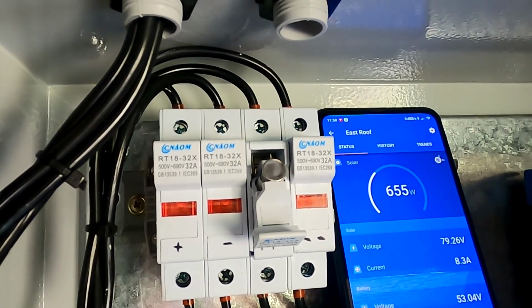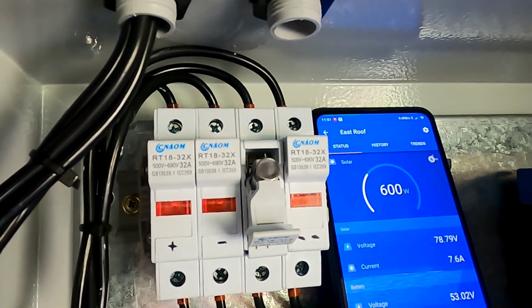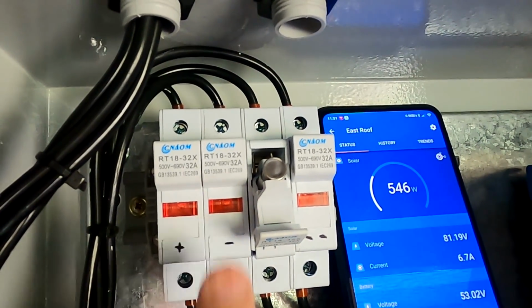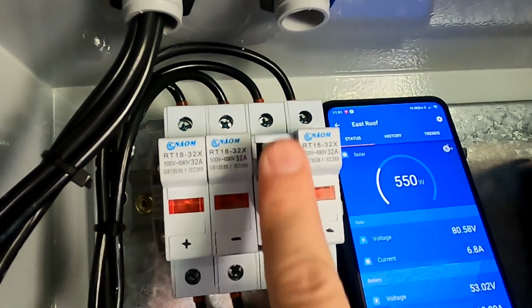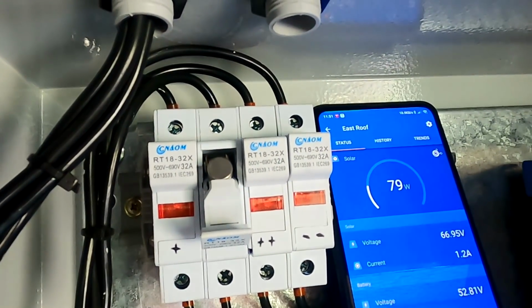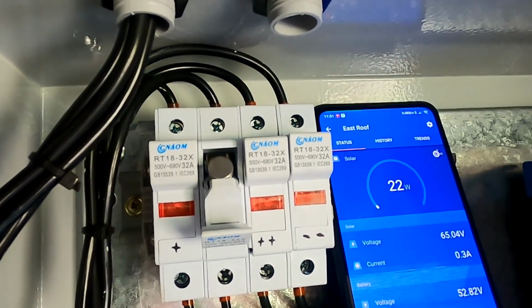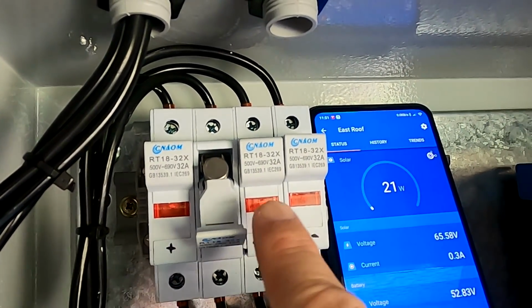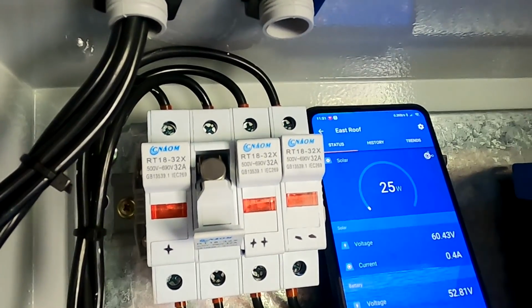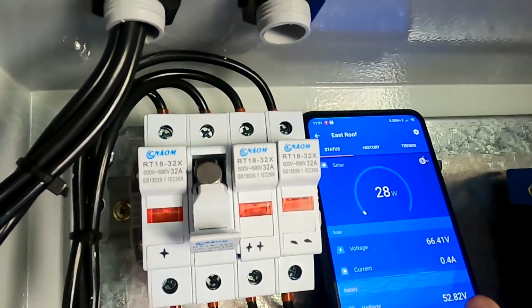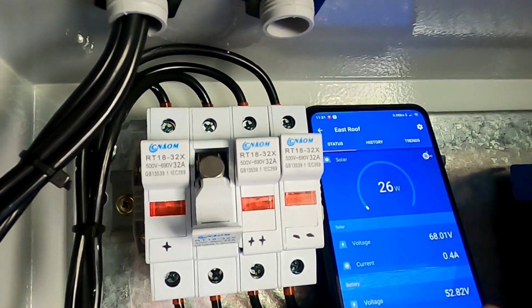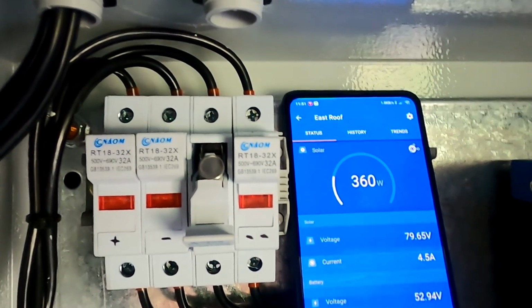So the sun is coming back now. 600 watts for the panel which is not shaded, and still 22 watts for the panel for the string which is shaded. So it's still delivering 0.4 amps. Okay, let's wait for the full sun.